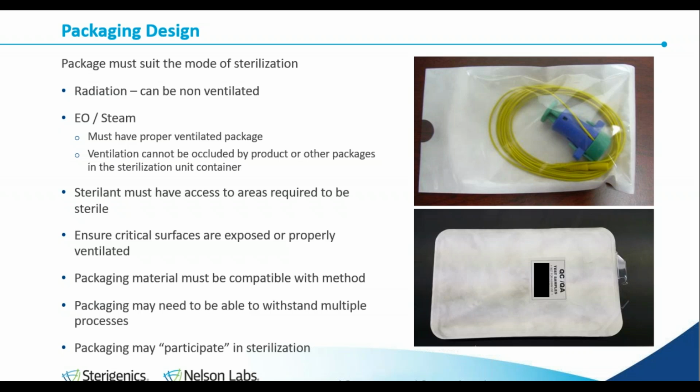And then finally, there have been some incredibly clever designs where the packaging itself participates in the sterilization. To give an idea, packaging could have vents in it, or could have components within it that can absorb moisture. It can actually have components in it that deliver your drug to the product under deep vacuum. There are many really clever designs that have been developed over the years where the packaging actually plays a role in the sterilization and even the creation of the final device for a pharmaceutical product, usually a combo device of some sort.